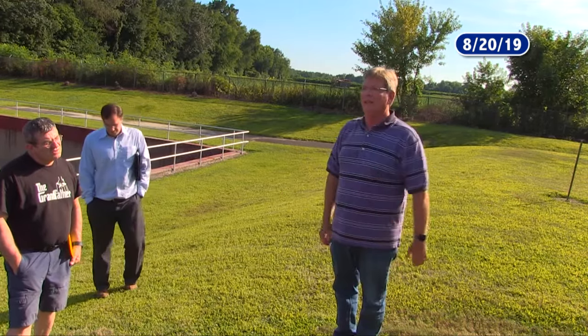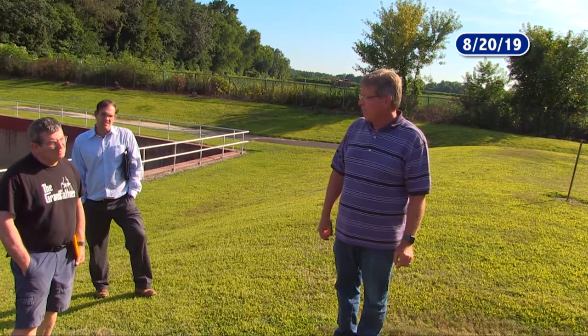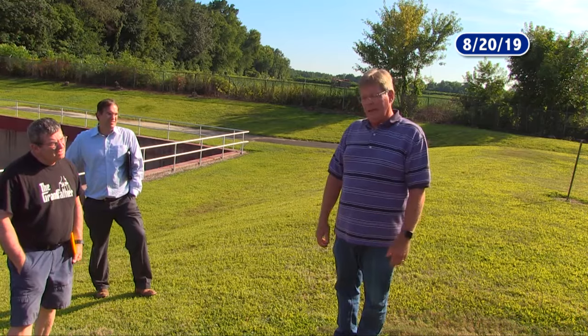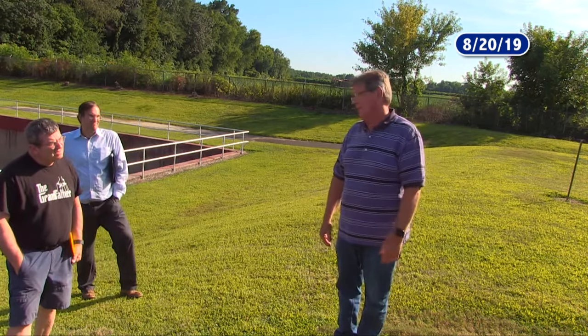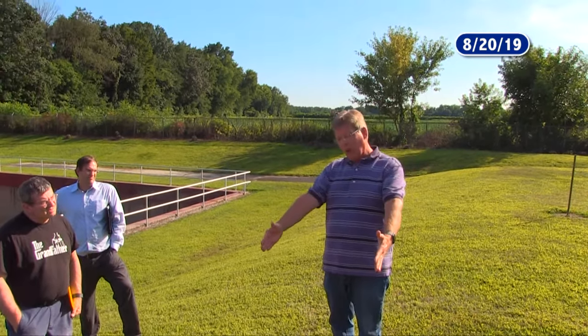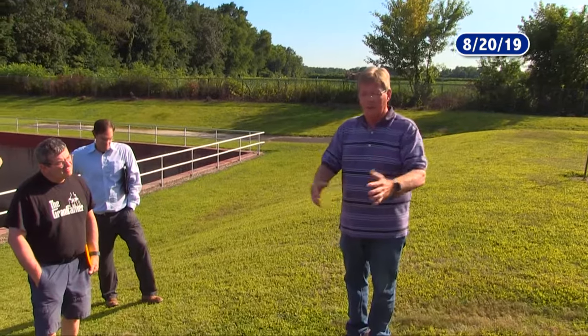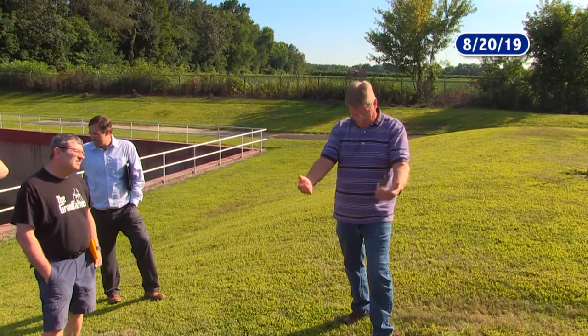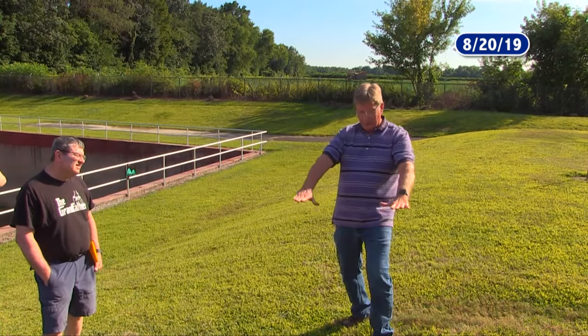And it just constantly comes in. So those sound like problems with users. How would a new system be different? The new system would include a full headworks building. And a headworks is something that's standard in the industry and has been for 30 years. It's a mechanical bar screen, and now they use fine screens, quarter-inch bar screens. So the influent would come in, hit this bar screen, and as it occluded the bar screen, the level would slowly rise.